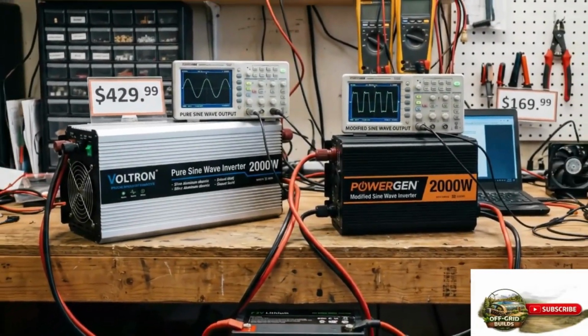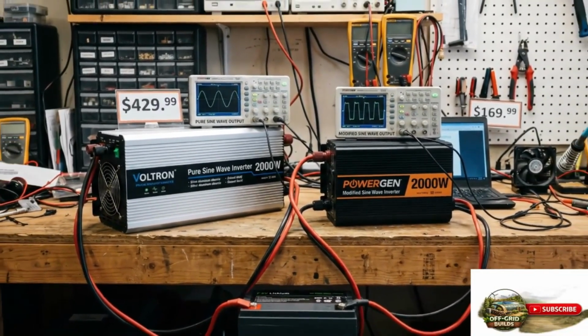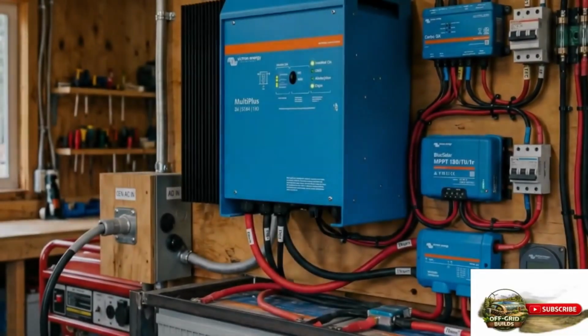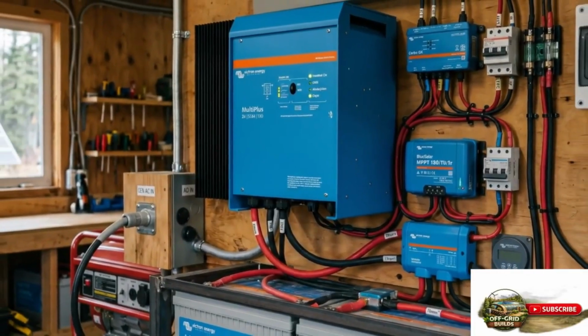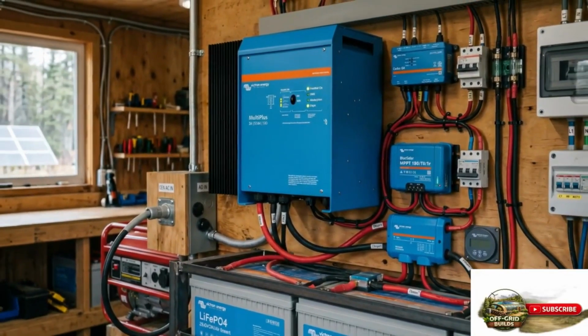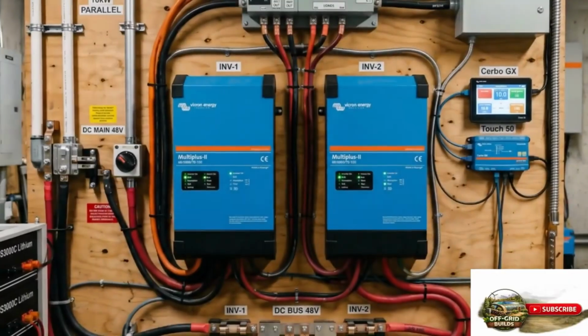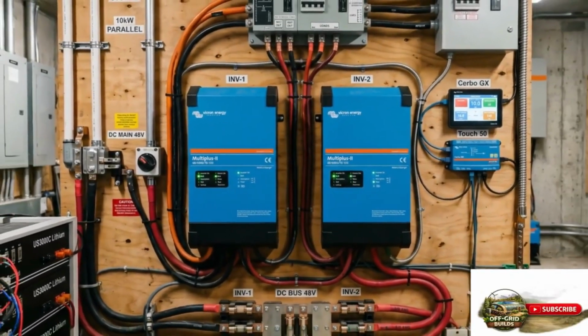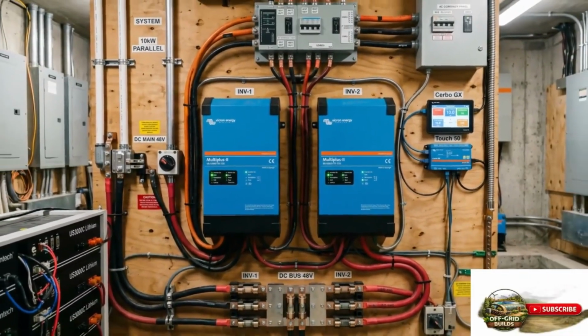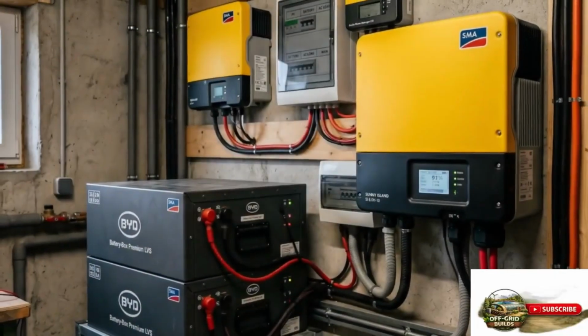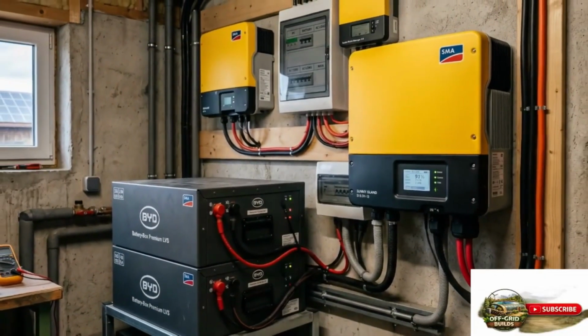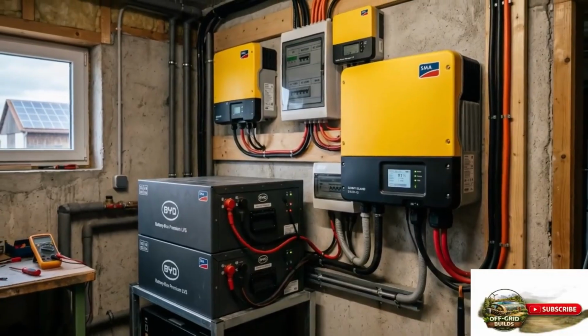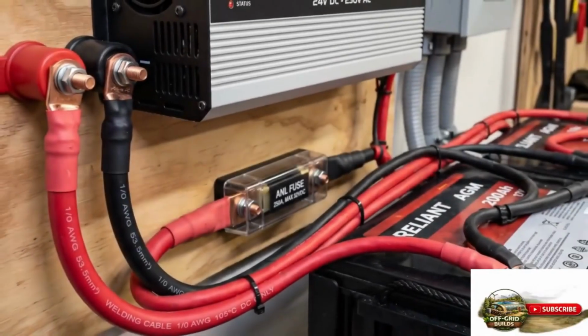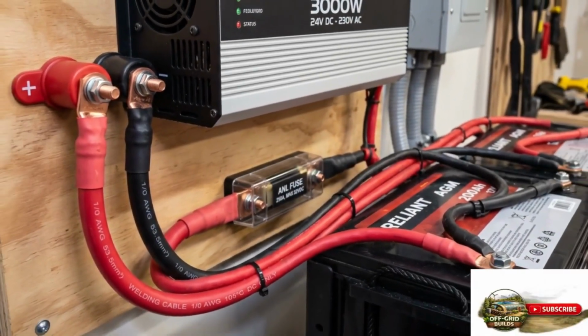A well pump starting up can draw 3 to 5 times its running wattage for the first second of operation. An inverter that cannot handle this surge will fault and shut down, which is a common frustration in undersized off-grid installations. For a 10,000-watt solar system serving a full household, an inverter rated for 8,000 to 12,000 watts continuous output with corresponding surge capacity is appropriate.